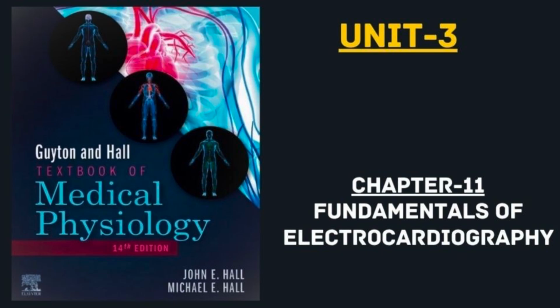I notice we're using the right arm, left arm, and left leg. What about the right leg? What's its job? Ah, the forgotten limb. The right leg electrode is just the ground. Just the ground wire, like on an appliance? Exactly. It doesn't participate in creating any of the views. Its job is to stabilize the recording and remove electrical interference, the 60-cycle hum from the power lines in the walls or the fluorescent lights in the room. It's just there to keep the signal clean. Poor right leg. No glory.